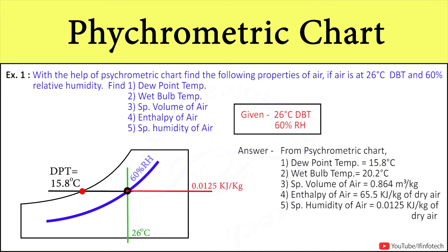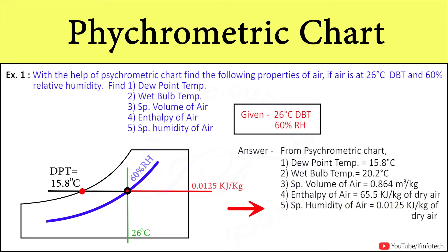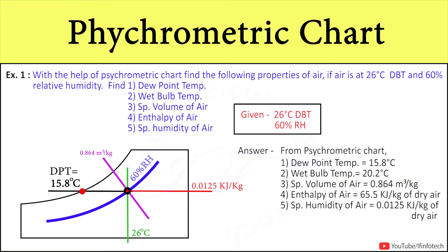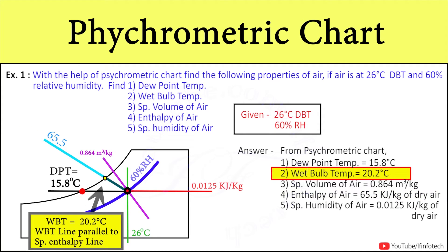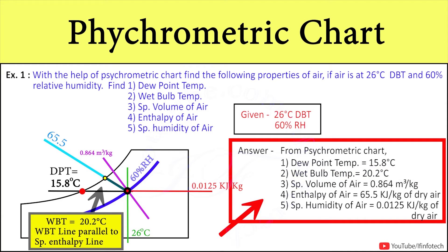Extending the line to the right side, specific humidity is obtained as 0.0125 kg per kg of dry air. From the specific volume lines, we get approximately 0.864 m³/kg specific volume, and from the inclined specific enthalpy line, enthalpy is 65.5 kJ/kg of dry air. In this way, with the help of the psychrometry chart, we can determine different properties of air at 26°C dry bulb temperature and 60% relative humidity.